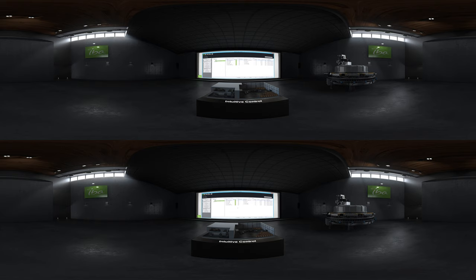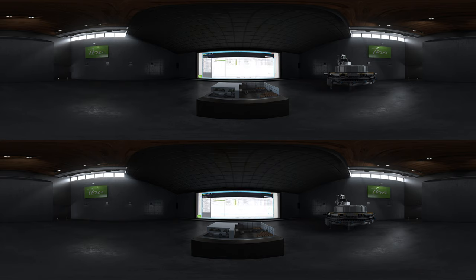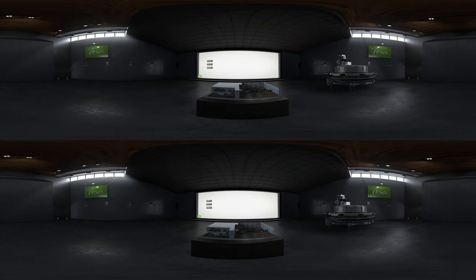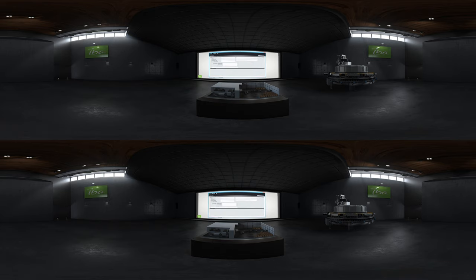Before starting an irradiation, you have to prepare offline the treatment recipe associated to a product. You need to define all the parameters like the beam current, the speed of the conveyor under the beam and the scanning length. All these parameters receive an upper and lower limit that define the validity of the treatment. After validating the treatment recipe, you need to create a batch order by associating a treatment recipe with a product or material and a path which defines the travel sequence of the product on the conveyor.